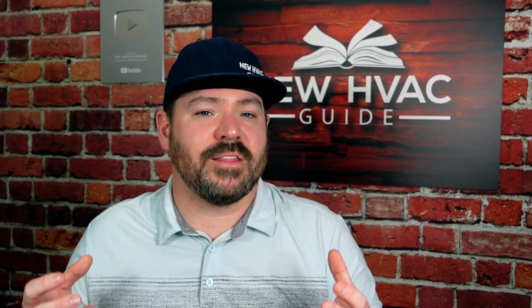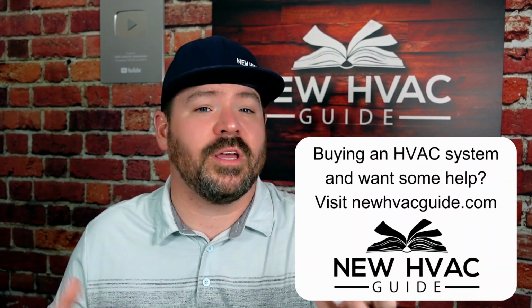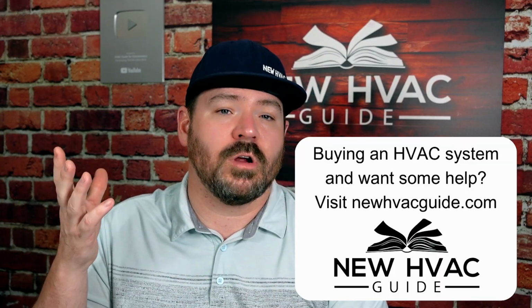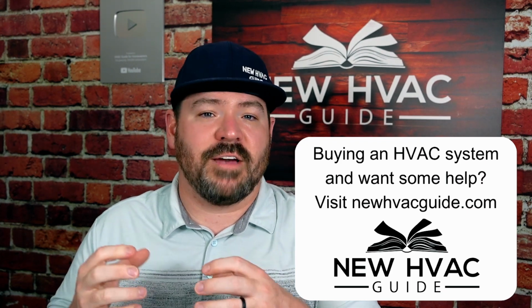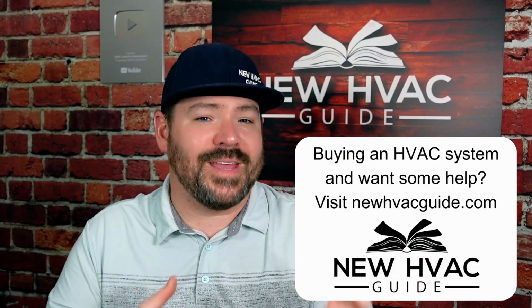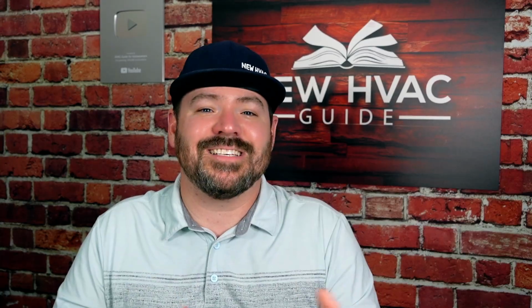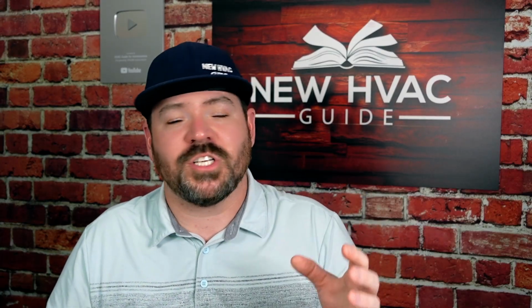What's interesting, and something a lot of folks don't understand, including pros in our industry, is not all mini split systems are created equal either, because some systems have very little variable technology in them. They may still be an inverter system, but because of the technology in that system, it may not ramp down as much, especially with a lot of the multi-zone systems out there.